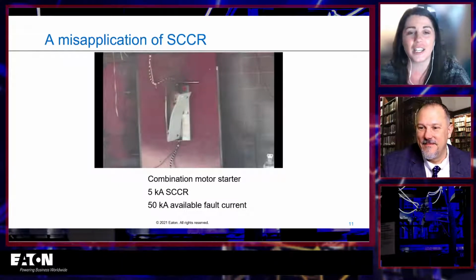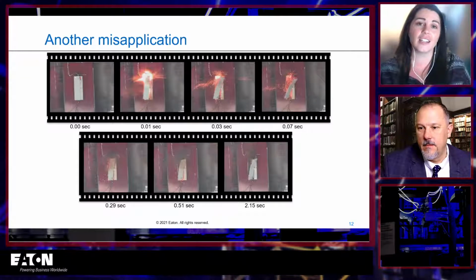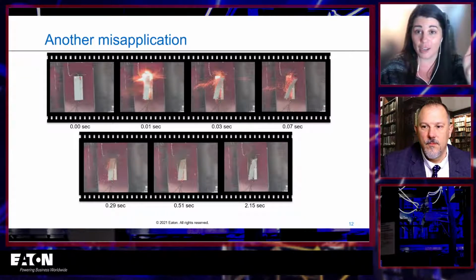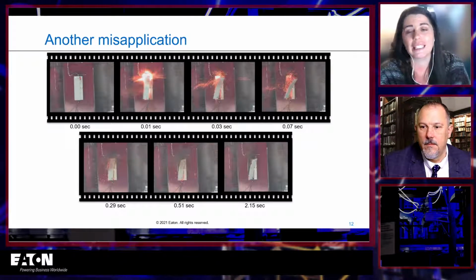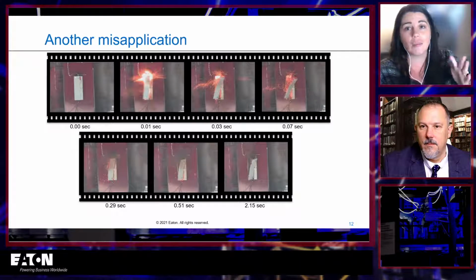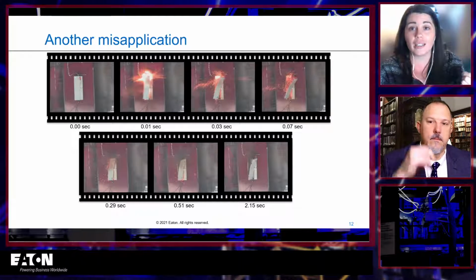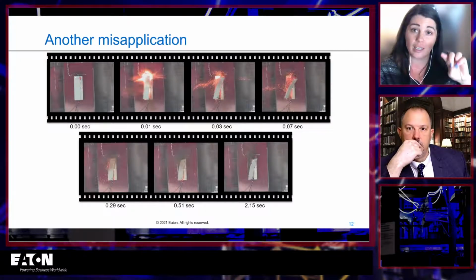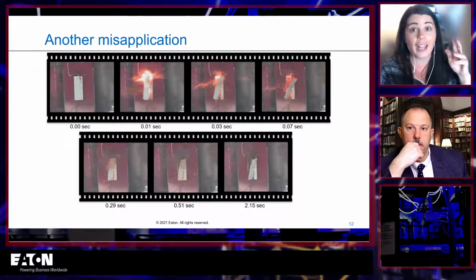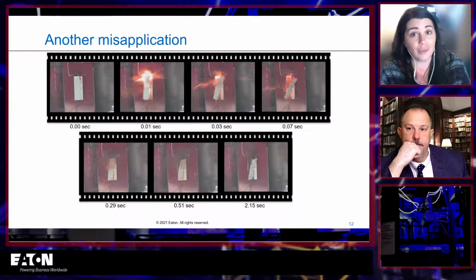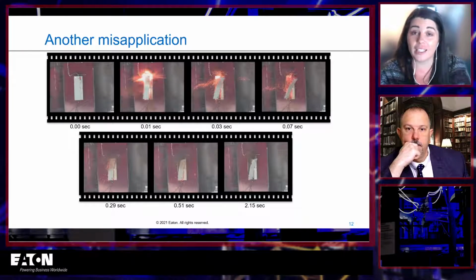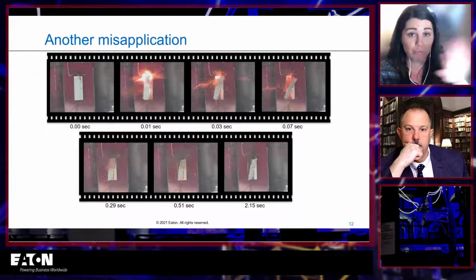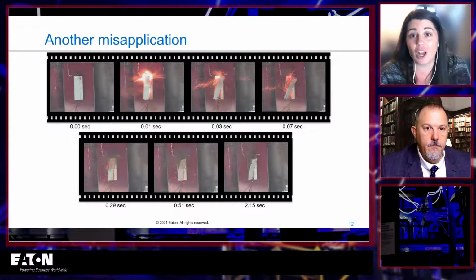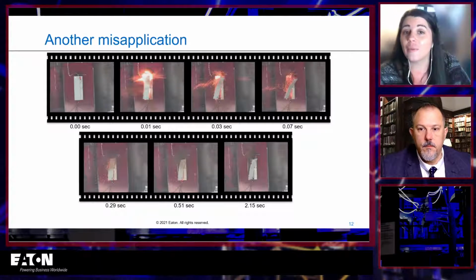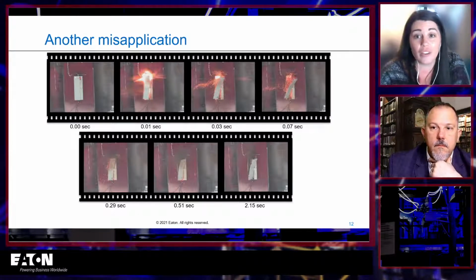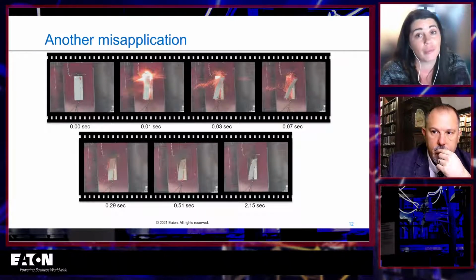So again, if you go to the next one here, we can see these still frames of this, and you can see right at 0.01 seconds, this is done for, right? Gone. No more. And this makes sense when you think about it, because the worst part of a short circuit is going to be the first peak, because in the real world, we tend to have asymmetrical short circuits. That means the very first peak is going to be the tallest. So the first half cycle, which is the first 8 milliseconds, give or take. So you're going to know immediately whether or not your equipment has passed or failed, right? You'll know within 8 milliseconds, because that's the most amount of energy it's going to see. So here at 0.01 second, we're done, right? There's certainly a fire and a projectile hazard here. We can't quite tell if we've created a shock hazard, but we've at least failed 2 out of 3 of our criteria, and likely 3, but at least 2.